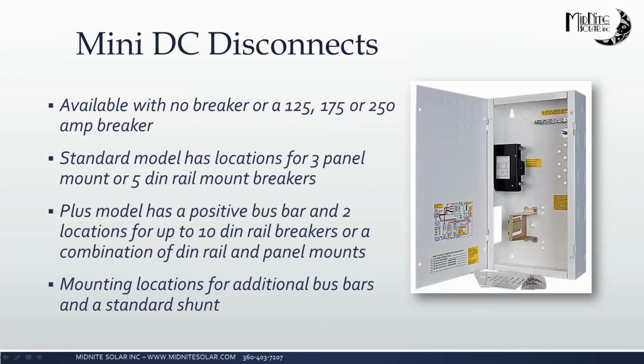Our mini DC disconnect. So this is one of our basic e-panels. It is designed to go with basically any inverter out there. If you don't want to go with one of the custom e-panels, this is a great fit. It's available with no breaker, a 125 amp, 175 amp, or 250 amp breaker already installed, which covers the requirements of most inverter manufacturers out there. The standard model has locations for either 3 panel mount or 5 DIN rail mount breakers. And if you upgrade to the Plus model, that gives you a space for a positive bus bar and 2 locations for breakers for up to 10 DIN rail mount, or a configuration of mixed 5 DIN rail mount and 3 panel mount.